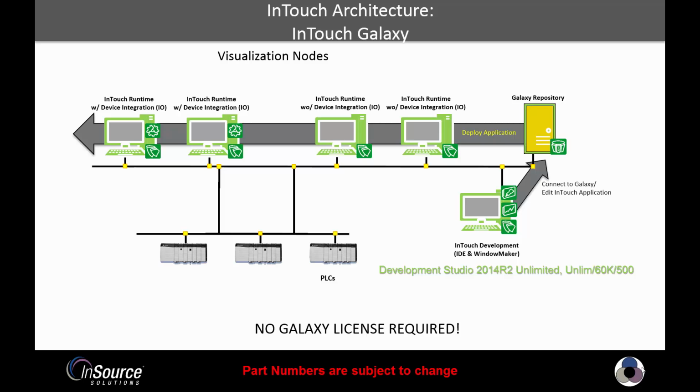What makes this special is the computers that are on the left, the InTouch runtime with device integration, means that that's where our drivers will reside and be used by the 2 computers on the right that say InTouch runtime without device integration. Here in this example, there is no Galaxy license required. Our development license allows us to pursue this route. Here are the part numbers for runtime with I/O and runtime without I/O.